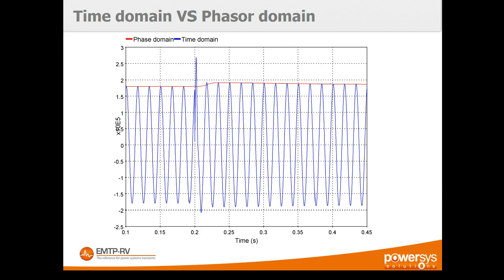In practice, the key difference between phasor domain and time domain software is what you see in the results. In phasor domain software you have access to the magnitude and angle of the phasor, whereas in time domain software you see the actual waveform of the voltage, current, and all electrical quantities — the exact same waveforms as those on a real network.